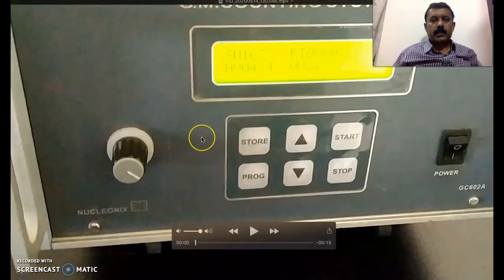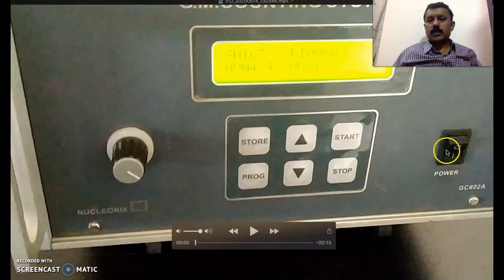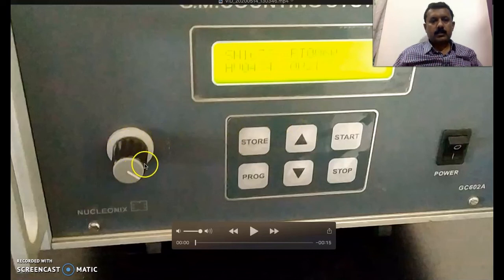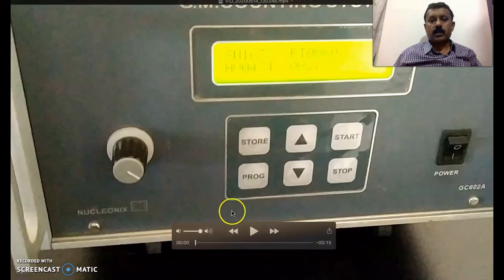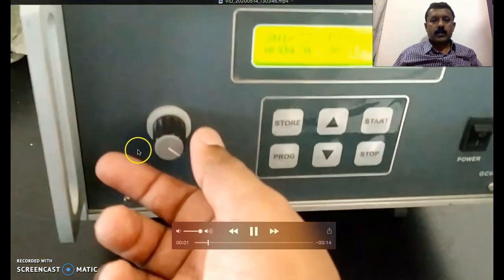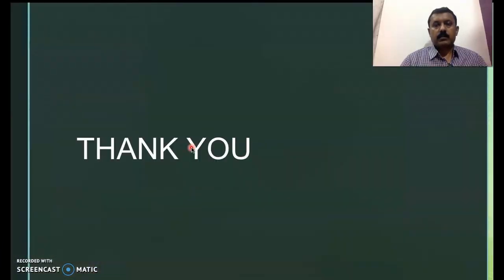After taking all readings, remember an important shutdown procedure: do not switch off the GM counter all of a sudden. The GM tube is very costly and must be safeguarded. Rotate the voltage knob gradually in the counter-clockwise direction to bring the voltage to zero before turning off the power. Vary this slowly.